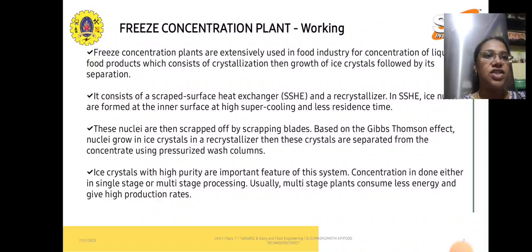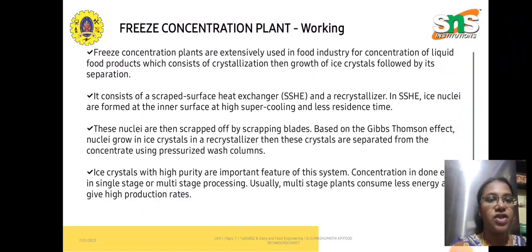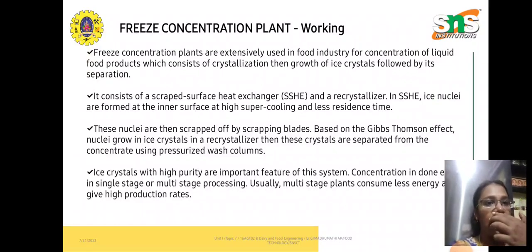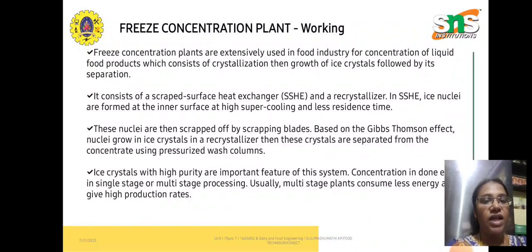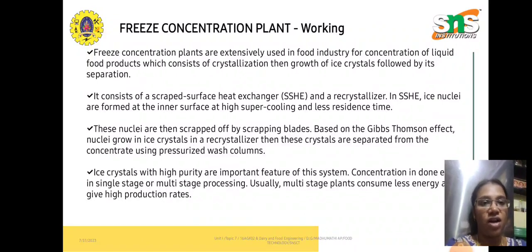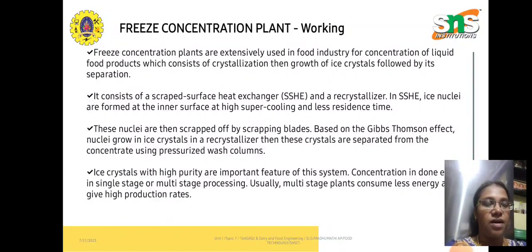These plants are used in the food industry for concentration of liquid products, involving crystallization and growth of ice crystals followed by separation. The scraped surface heat exchanger (SSHE) forms ice nuclei at the inner surface under high supercooling. These nuclei are scraped off by scraping blades, and based on the Gibbs-Thomson effect, the nuclei grow into ice crystals in the recrystallizer. These crystals are then separated from the concentrate using high-pressure water columns, producing high purity ice crystals.